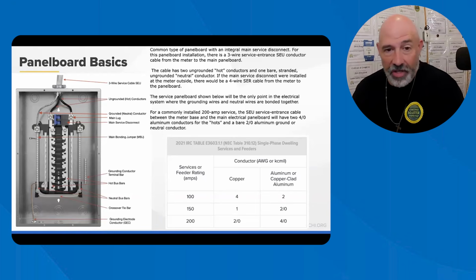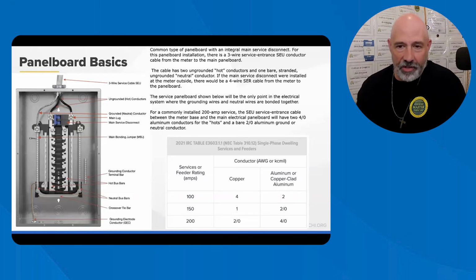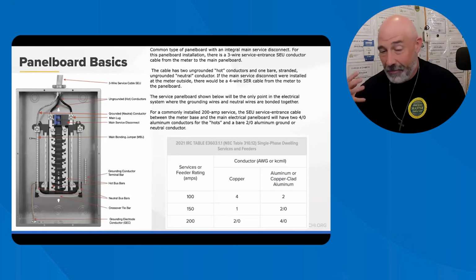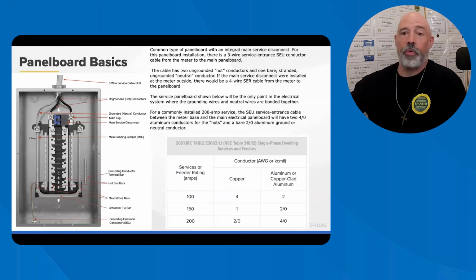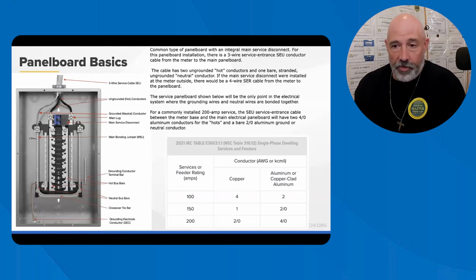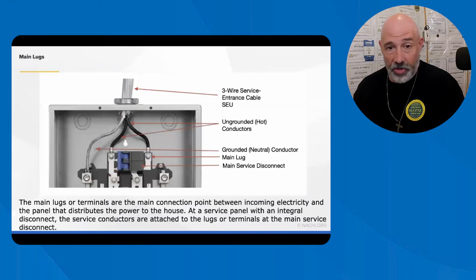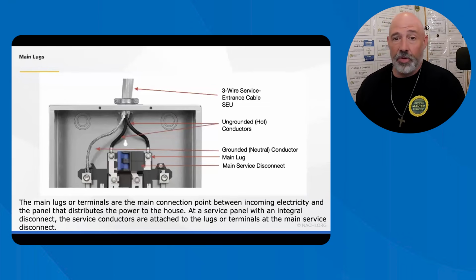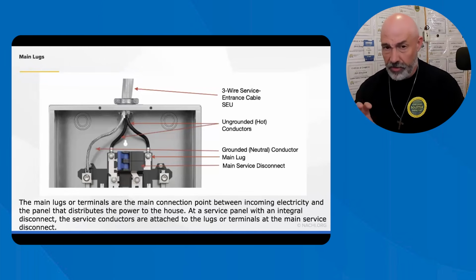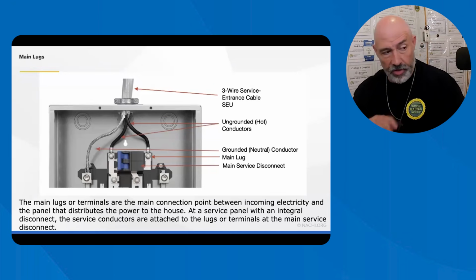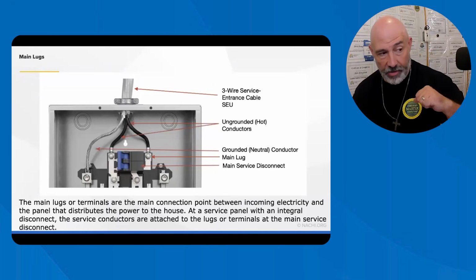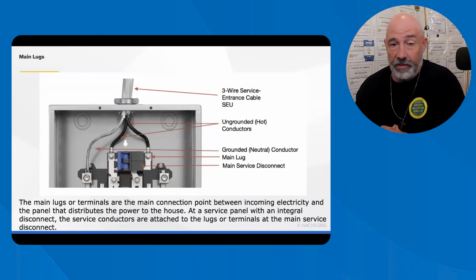And if you want to take a screenshot of this, there's only one location in the electrical system where neutrals and grounds are bonded, and that's the main panel. We've already had tons of questions about that. A typical 200 amp service commonly uses number four aluminum conductors for the hots and a 2/0 for the neutrals and so on and so forth. So just know the main lugs or terminals are the power that enters into the panel. Look at those, make sure that they're not burned or anything like that. You want to make sure that you shine your flashlight on there, make sure that it's not corroded or burned or anything like that. I've seen that quite a bit.